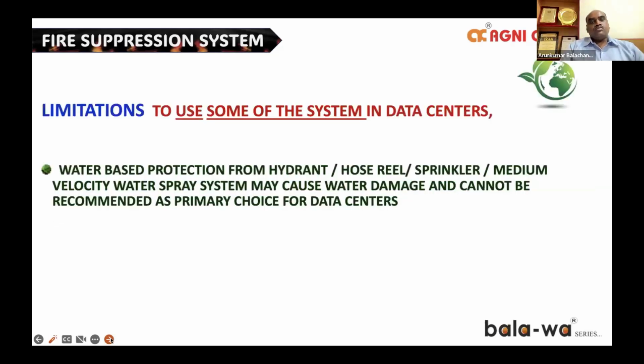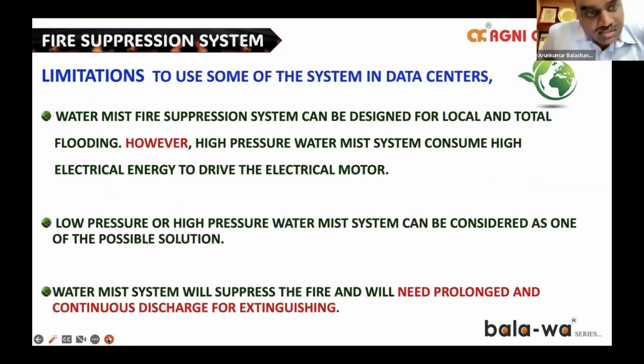We'll now come to some of the limitations of the suppression systems. Any water-based hydrant, hose reel, or sprinkler cannot be used, and there is no recommendation for that in a data center. We'll go in for a water mist. We'll go in for the next system, which is the water mist system.